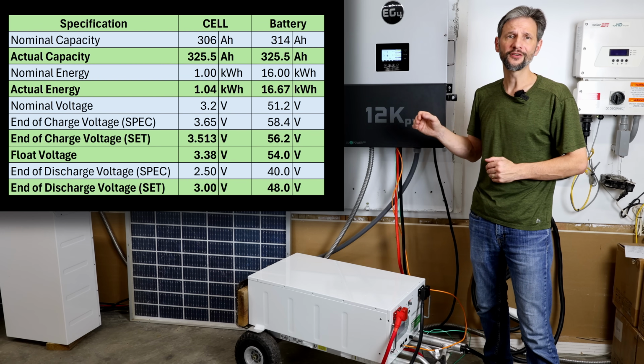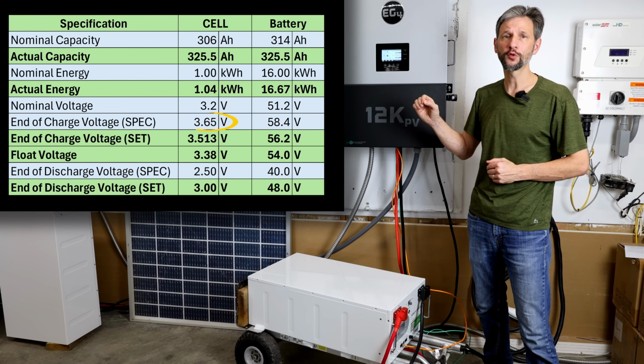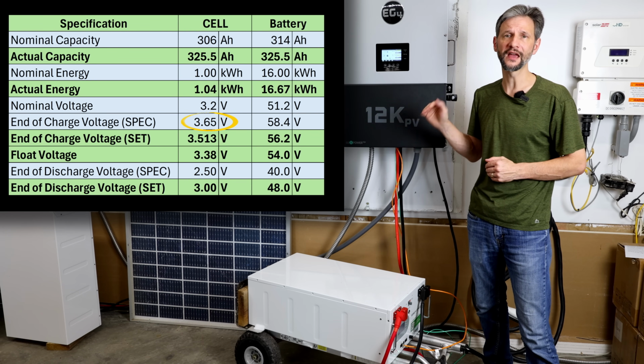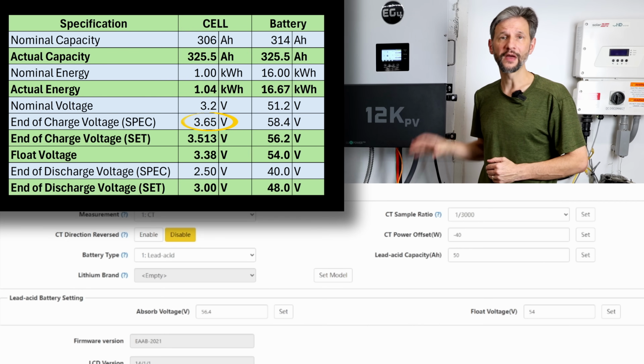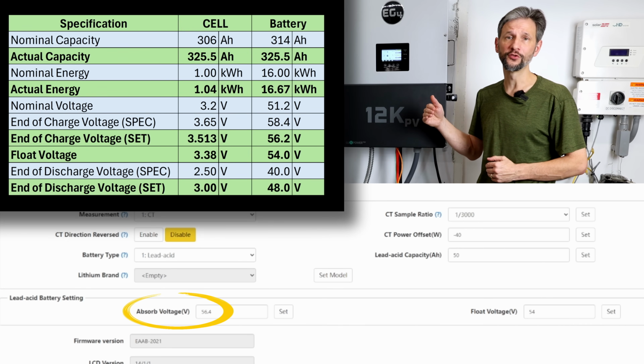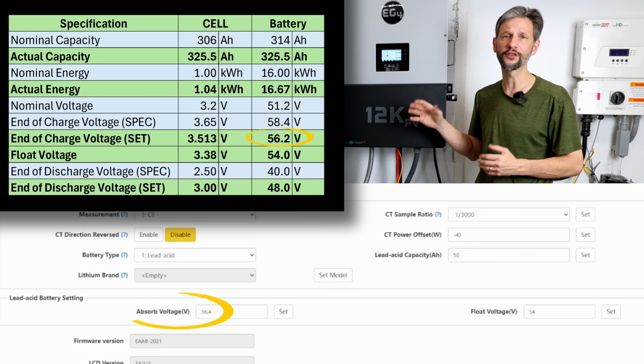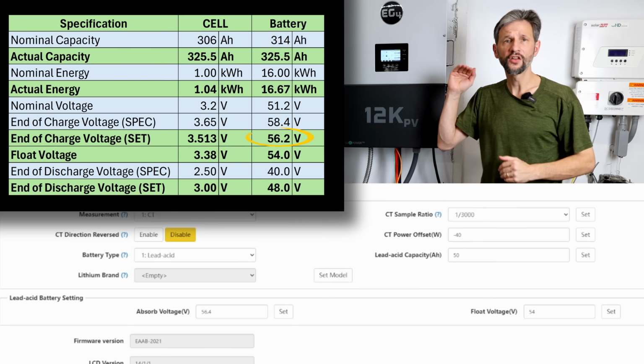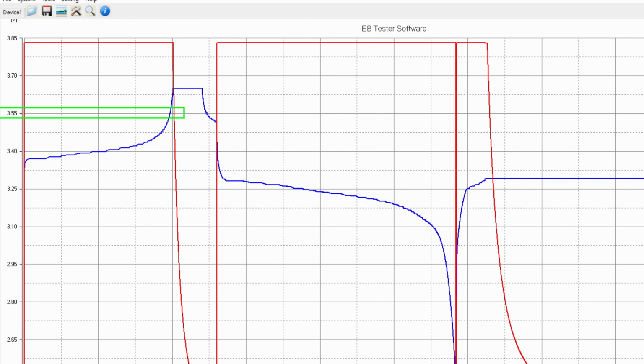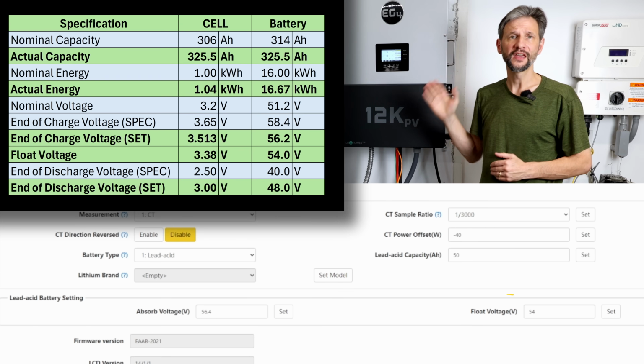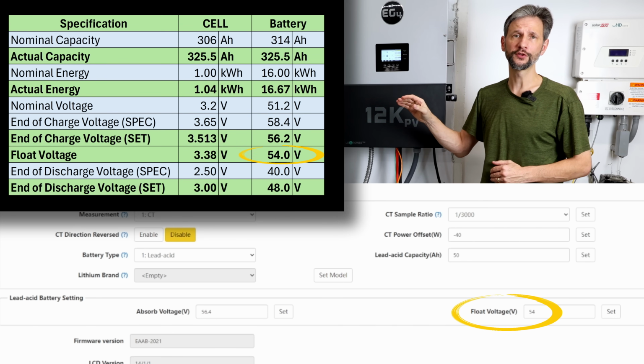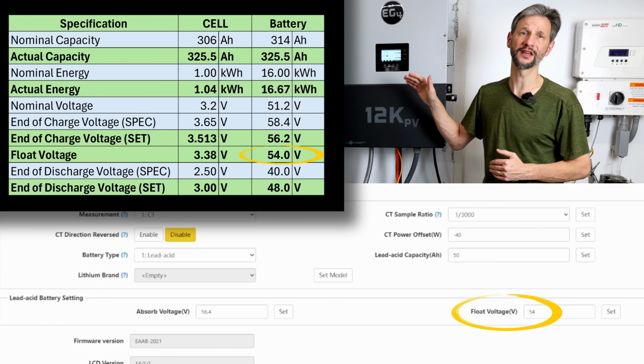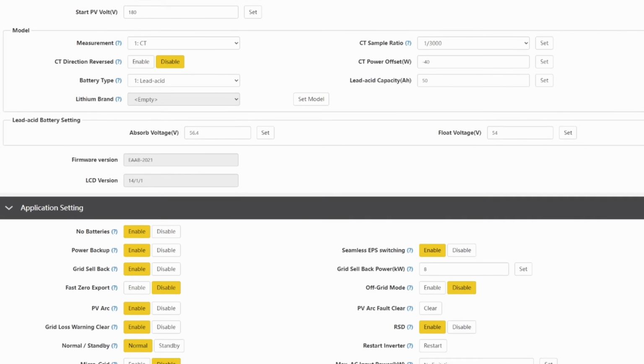The spec sheet calls out an end of charge voltage of 3.65 volts, which should be the maximum voltage in the BMS. For the battery pack, this is the absorb voltage, and I'll set that to 56.2 volts, which is equivalent to about 3.5 volts at the cell level. On the battery charging curve, you can see that this is well above the flat part of the charge curve to allow for balancing. Then I set the float voltage to 54 volts to prevent it from constantly running a charge cycle. Now we use the end of discharge voltage from our chart.